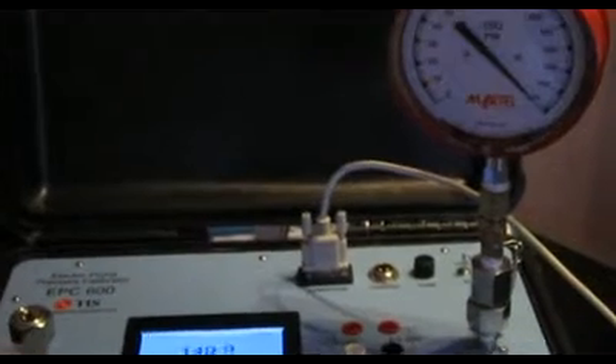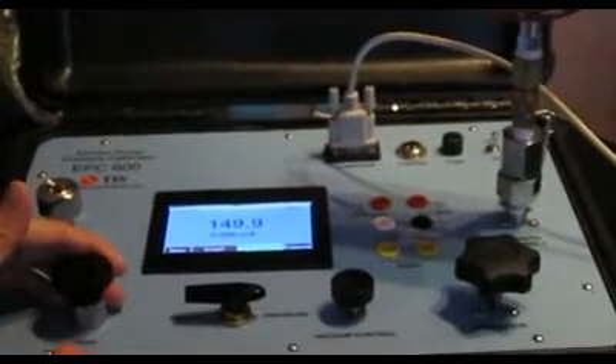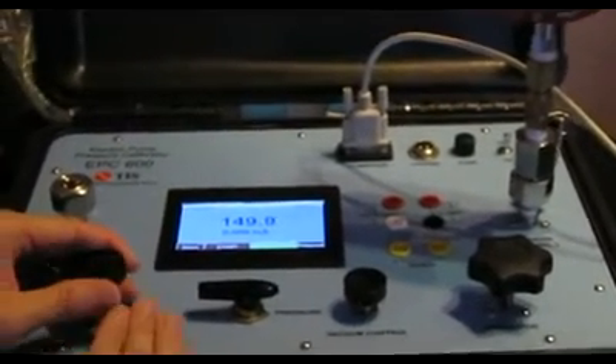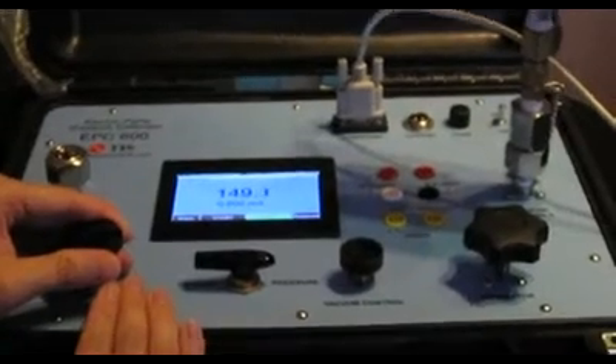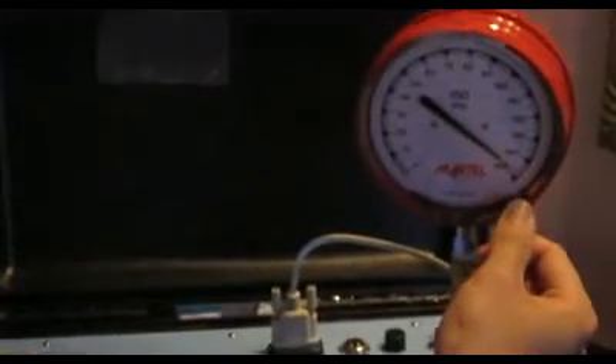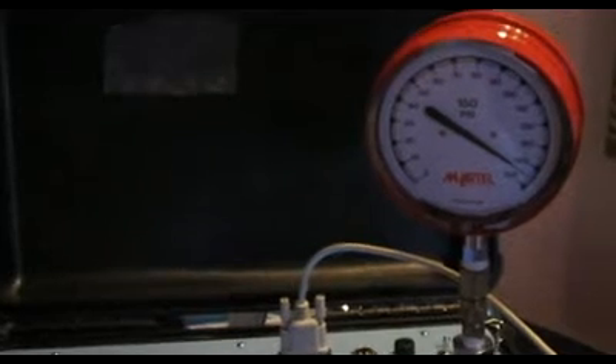Now we will do the descendings. Next point is 100 psi. We will use the vent valve. Simply, it's a needle valve. Simply tap a little bit and release the pressure. The pressure can be controlled very finely, or we can increase a little bit with more flow. At 100, we will close the valve and press enter.